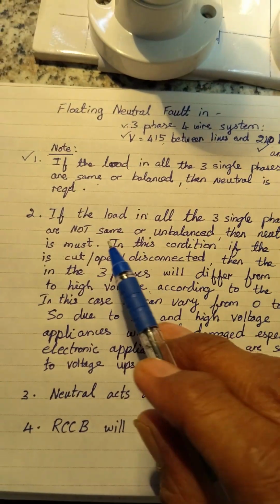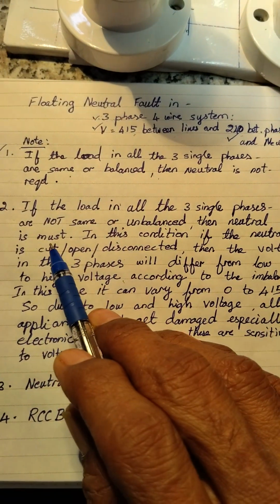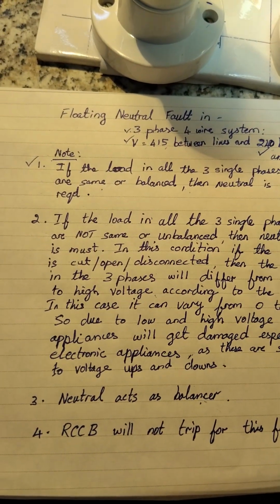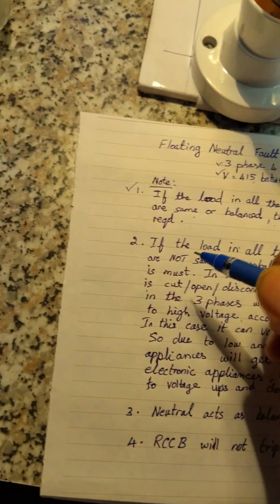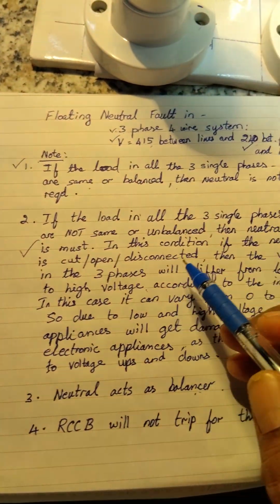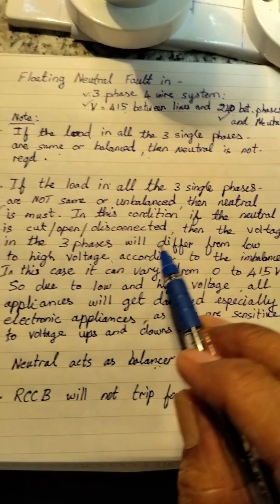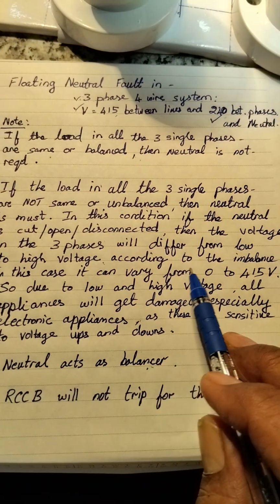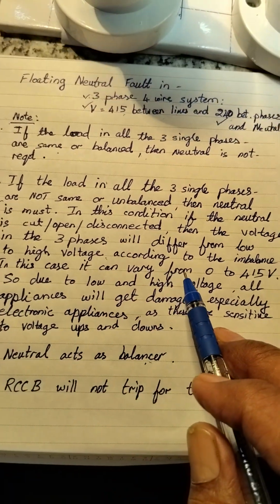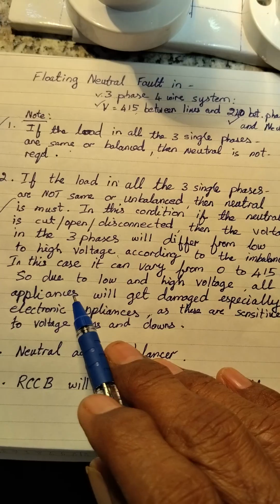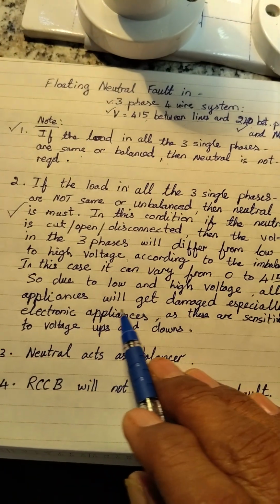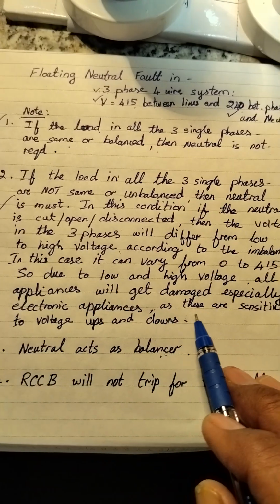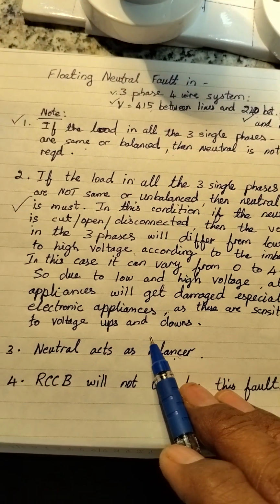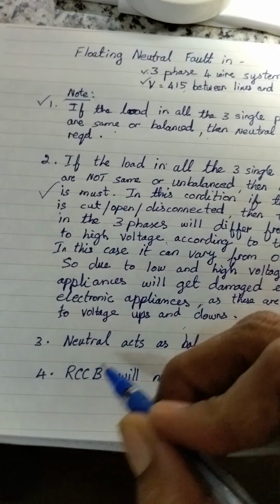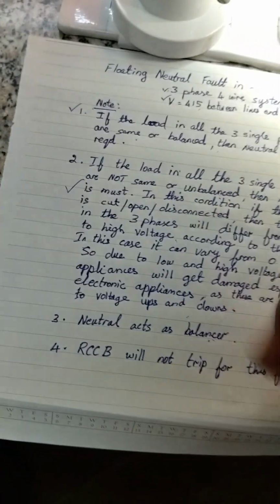So we have seen if the load in all the three single phases are not same or unbalanced, then neutral is a must. That we have checked now. The voltage differs from low to high according to the imbalance. In this case, it will vary from 0 to 415, we have seen. So due to low voltage and high voltage, all appliances get damaged, especially electronic appliances, as they are sensitive to voltage ups and downs. Then the third point, neutral acts as a balancer, we have seen.